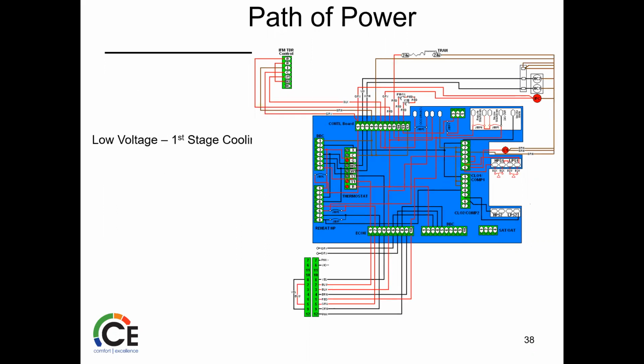So first stage cooling. Obviously we're going to get 24 volts to Y1. Then it's going to run through the economizer. If you don't have one, it just has that bypass plug in there. And then it's going to jump from, it comes in a blue wire, comes out a gray.